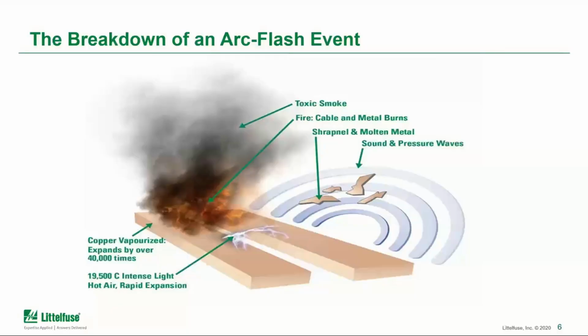And with that heat, the copper bus bars and the other materials go through very rapid expansion. And as it's moving from solid to vapor, that itself creates the explosion. And then you have projectiles of molten metal and other things that are flying. And one thing that's maybe not always talked about: when you're standing in front of that cabinet and an arc flash occurs, the first human reaction is to involuntarily inhale. And when you do that, when you have those gases and the molten copper particles, that can do a lot of damage to somebody who's standing there as well.